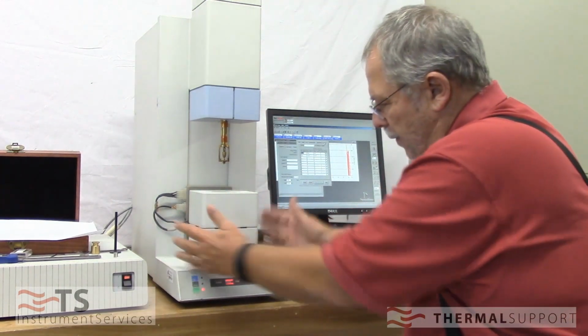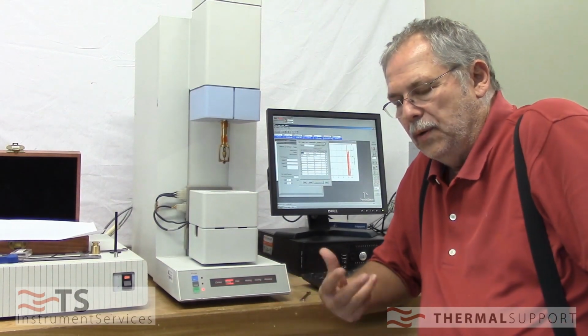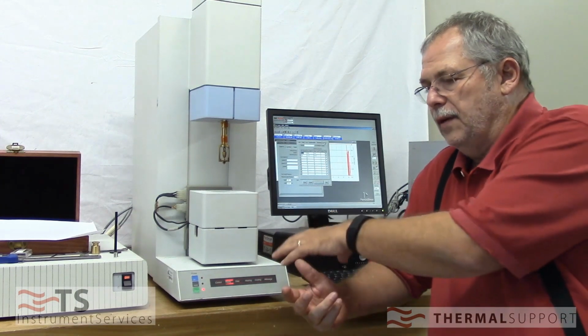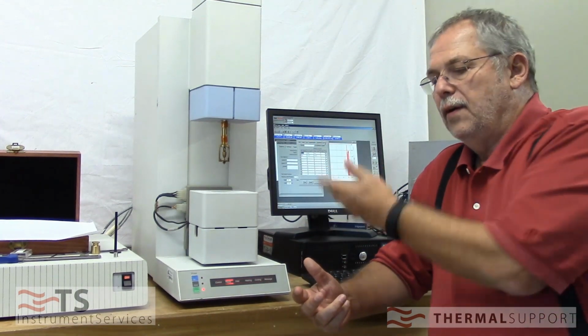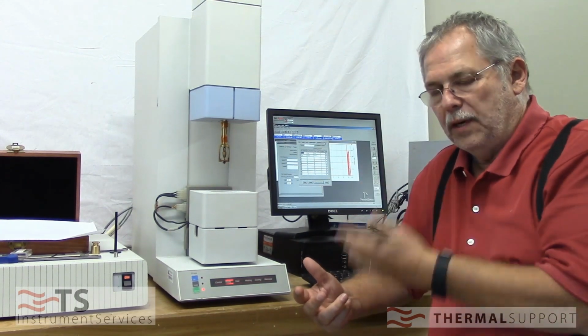that goes on here. And when you do the temperature in the furnace cal, when you have that dewar, you can do what we do in the shop, where we just simply use a coil of copper and put it in there and run a liquid through it. But you also can take out the dewar liner. You can put a block of ice in there and then put it back in and run it. You'll need a fresh block of ice for the furnace calibration.